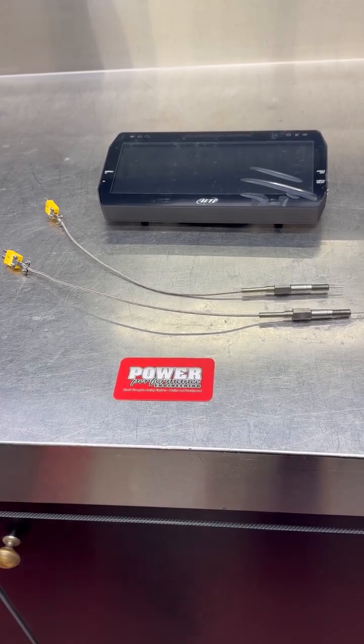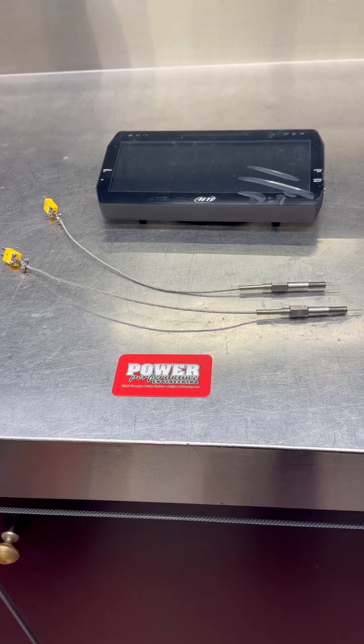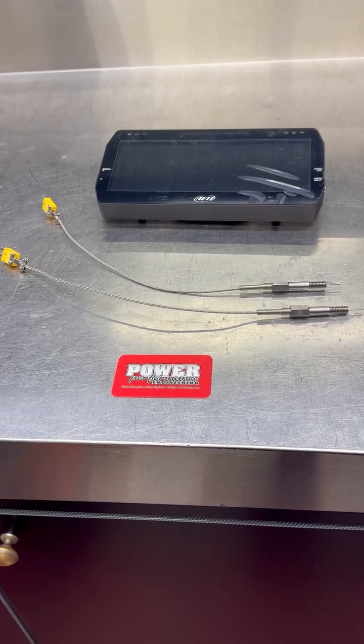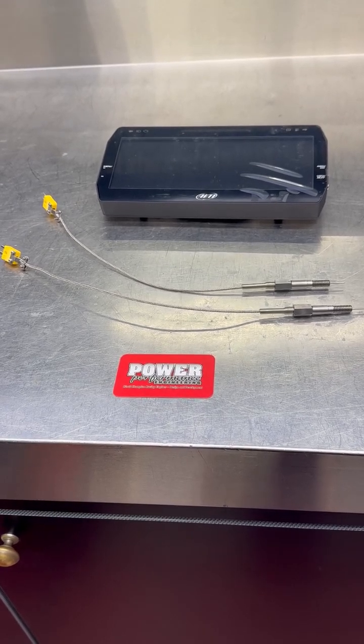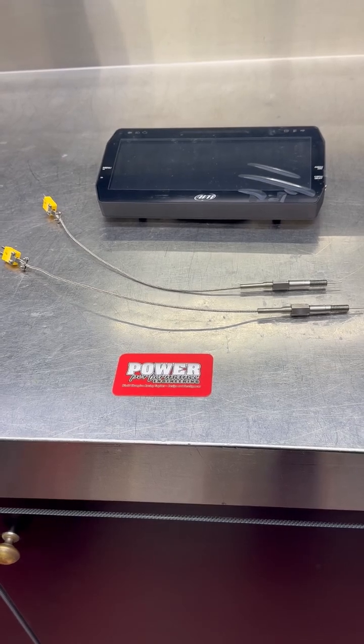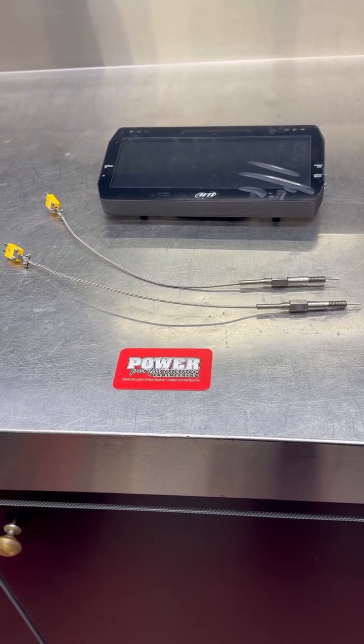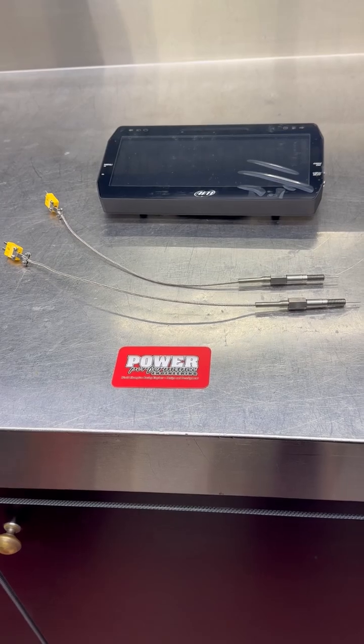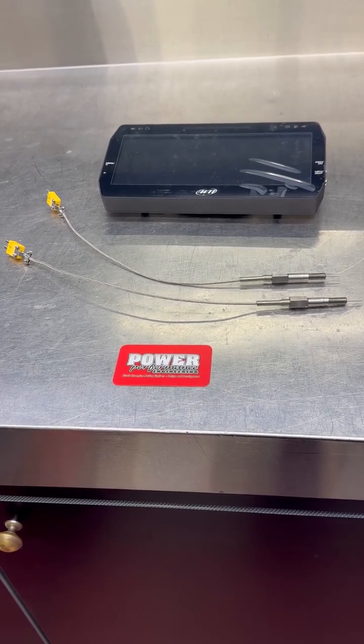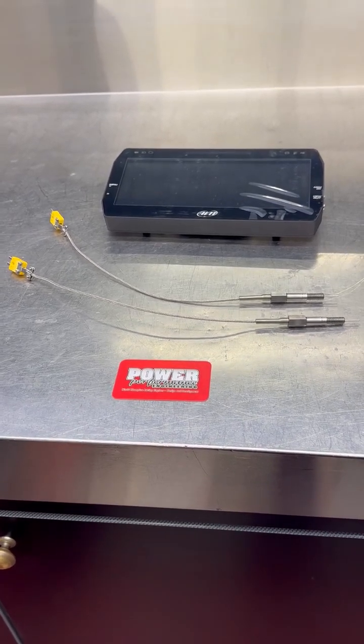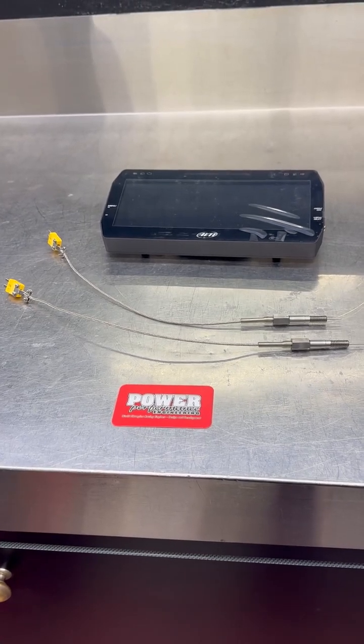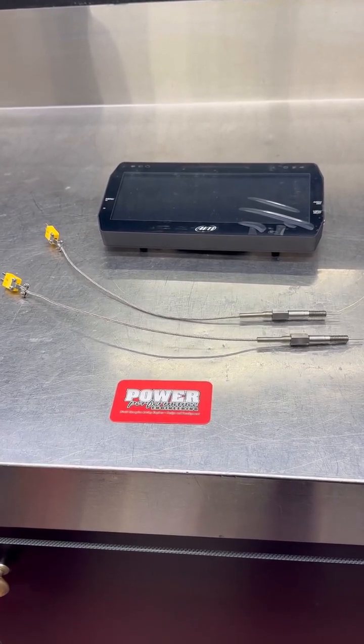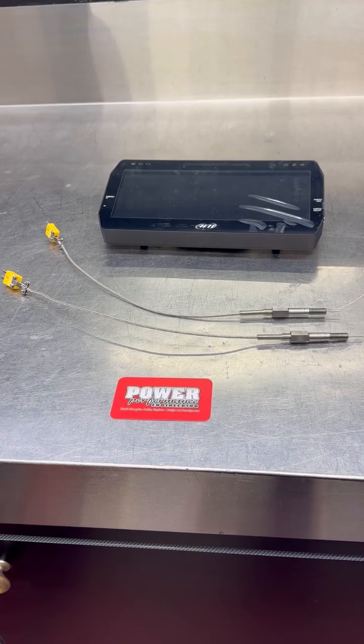Next thing is the range of these thermocouples on a K-type is minus 328 degrees to 2,300 degrees. So if you're trying to measure head temp, it's probably about the worst setup you can use, simply because the temperature range is far too wide to get repeatability as far as air temp, head temp, anything sub 200 degrees.